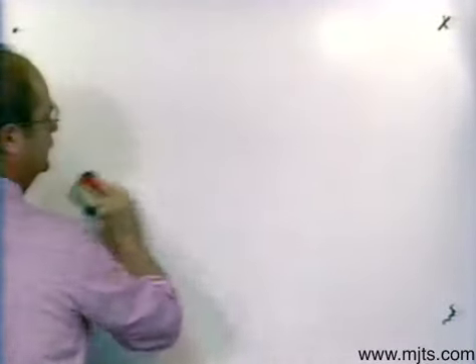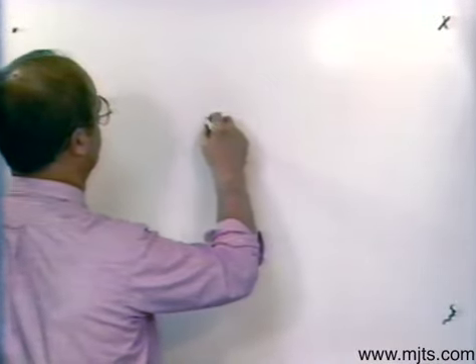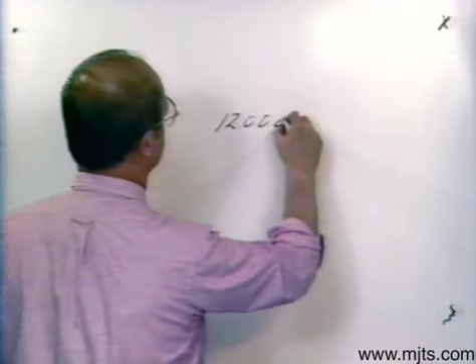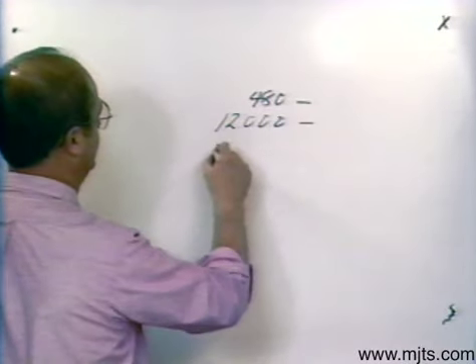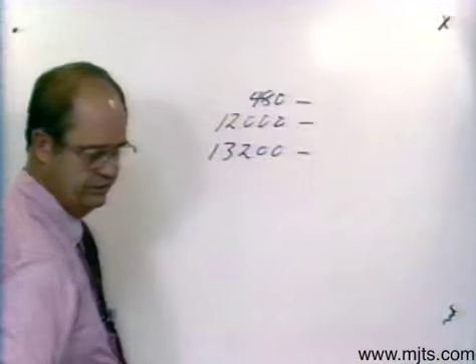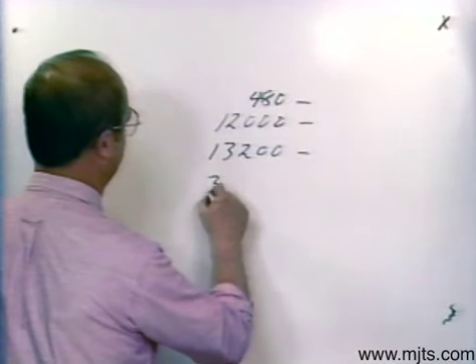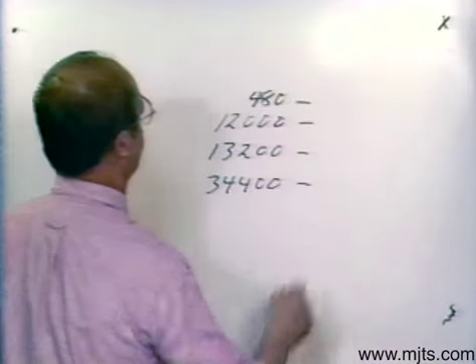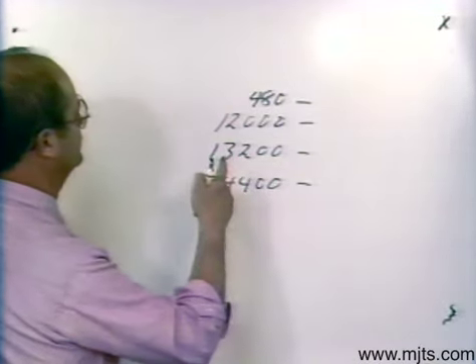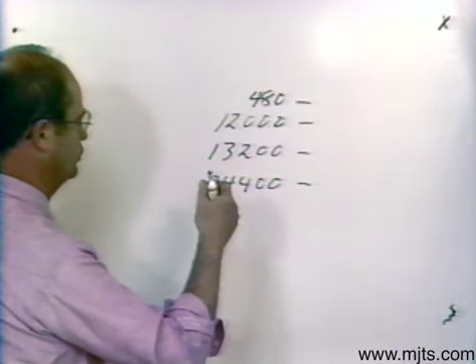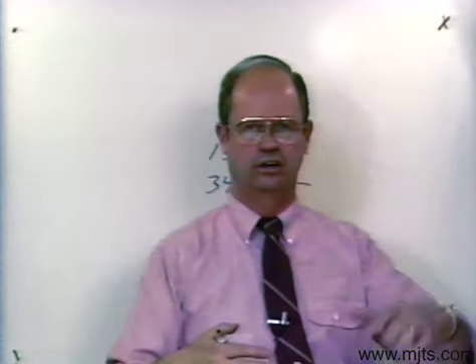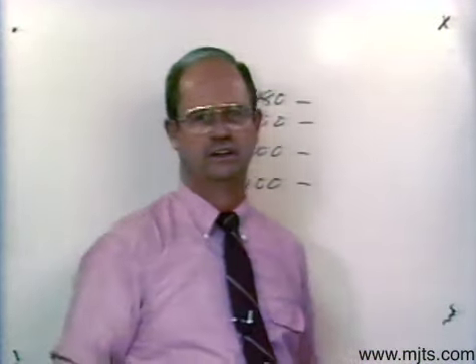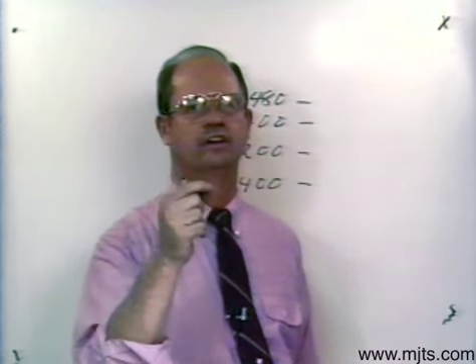The next type is written like this: 12,000 dash, 480 dash, 13,200 dash, 4,400 dash — and so on. When a rating is written with dashes only like that, it means the transformer is good for a delta connection only, which means high voltage and lower current, meaning the conductor size is probably smaller. For example, with a 480 volt service feeding a consumer, you could connect the high side at 480 and step down to 240/120 volt with a dry type transformer. These are good for delta only.